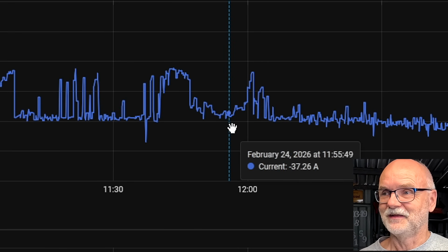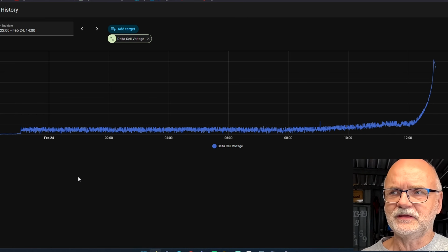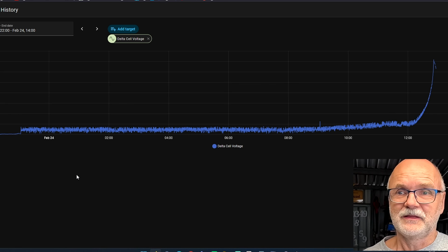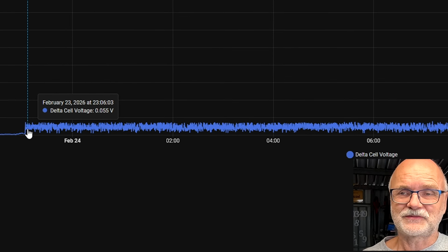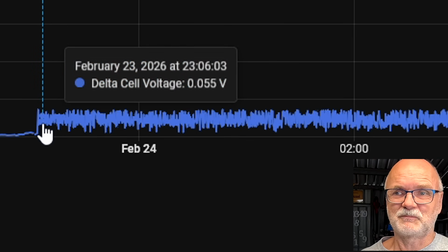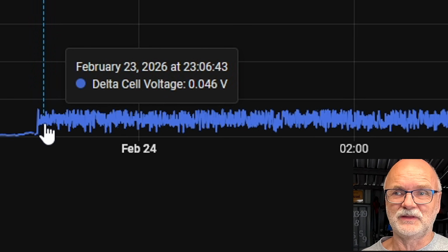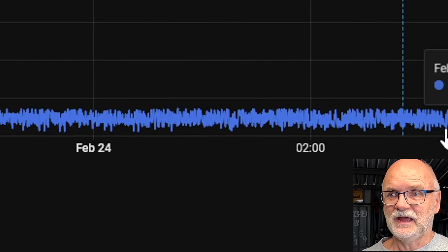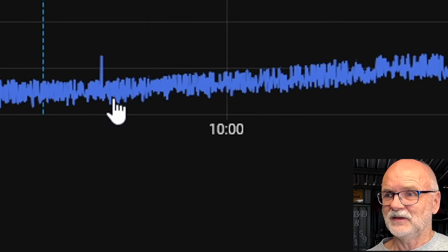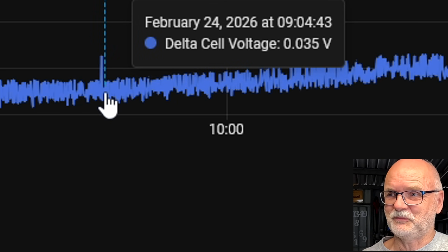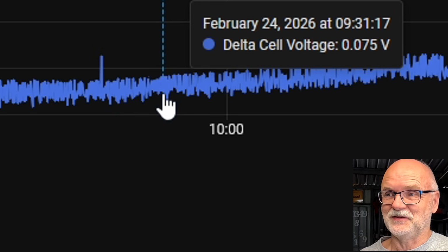So pretty interesting. But we can also have a detailed look at the cell voltage delta over the period of the discharge of this battery. We're starting here at somewhere around 30 to 50 millivolts deviation during the whole discharge, and this stays fairly constant. There's one little spike here, for whatever reason — could be a measurement error as well.